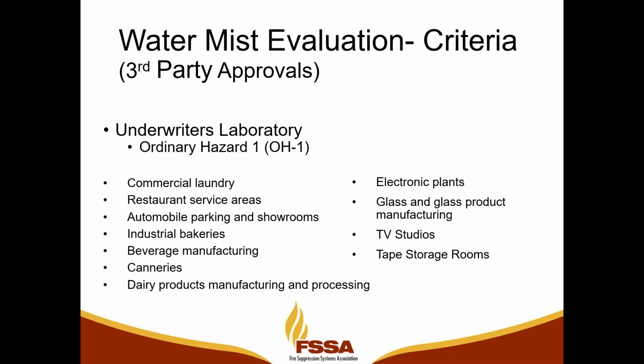For Underwriters Laboratories, as I mentioned before, there are ordinary hazard listings for a water mist type of system, mainly for ordinary hazard 1 or OH1. I put a couple of examples in here from the definition in NFPA 13, which is widely used to define this particular type of hazard. These are some of the different applications that you would see as part of OH1. The hazard classification would always be determined by the design engineer or the authority having jurisdiction for the area to be protected. So these OH1 areas could be automobile parking and showrooms, industrial bakeries, canneries, tape storage rooms, and electronic plants, just to name a few. Next slide.